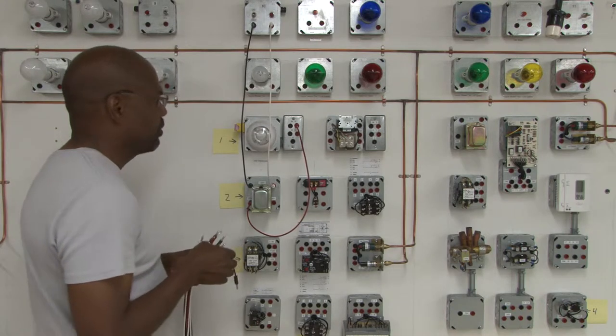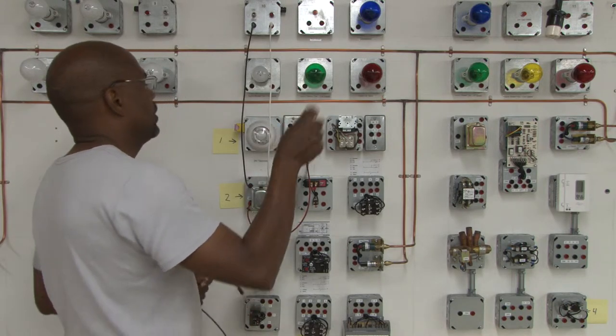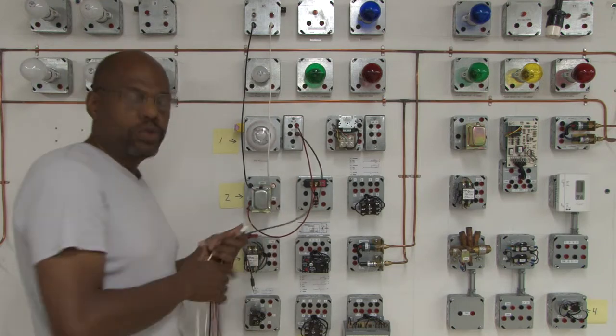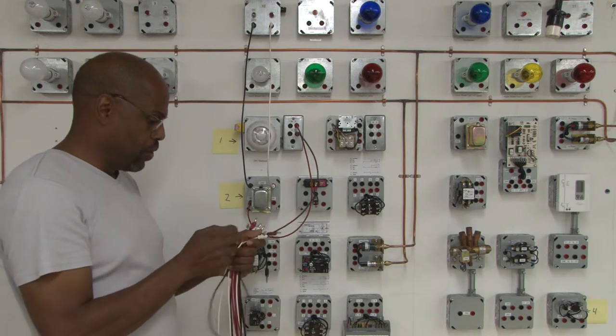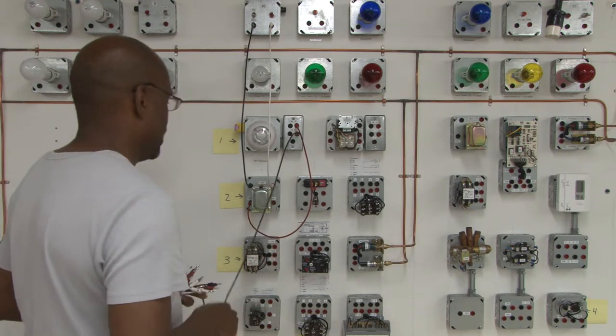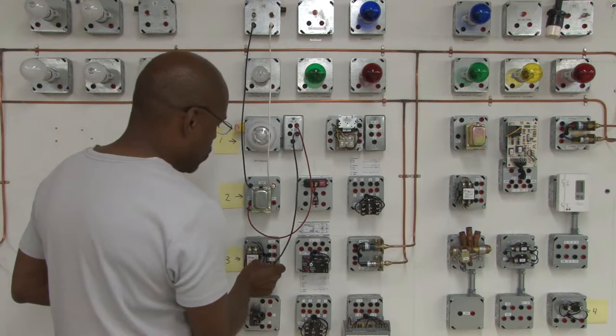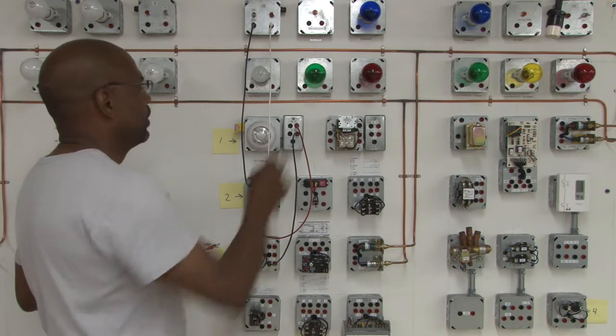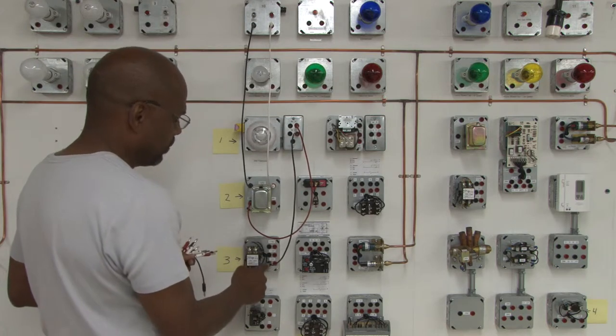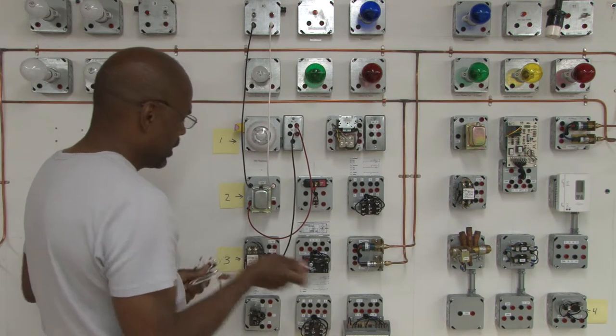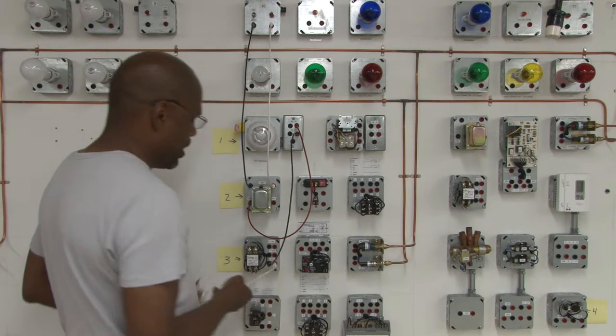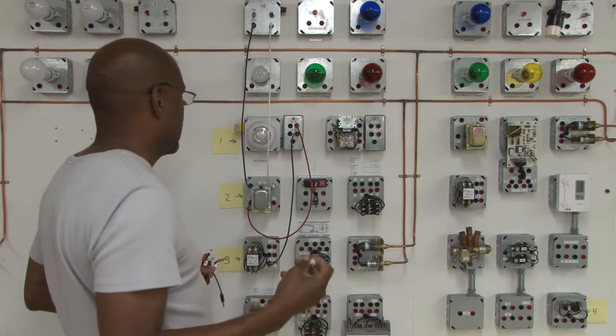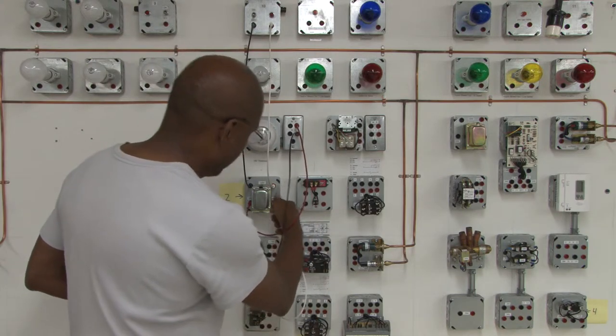We're going to come out of the thermostat and use Y. The terminal Y is used for air conditioning. So we're going to go to our coil of our contactor from Y terminal which is outlet and it goes to that side. Coming out the other side of the coil we're going to go back to the 24 volt side.